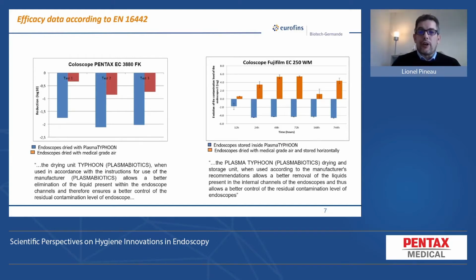We have done some tests to verify that this system is able to dry endoscopes and maintain the quality of the endoscope. The principle of the test is very simple. In fact, we contaminate two endoscopes with about 1,000 bacteria. Then one of the endoscopes is dried with medical grade air and stored horizontally. And the other one is dried and stored using the Plasma Typhoon system. As you can see with the test done with the PENTAX, for the endoscope dried with medical grade air and stored outside the Plasma Typhoon system, we obtain a reduction of the contamination of about 1 log, no more than 1 log. And if we use on the other side the Plasma Typhoon system, what we observe is that we can reduce the contamination by at least 2 log for one assay and around 2 log for the 2 other assays.